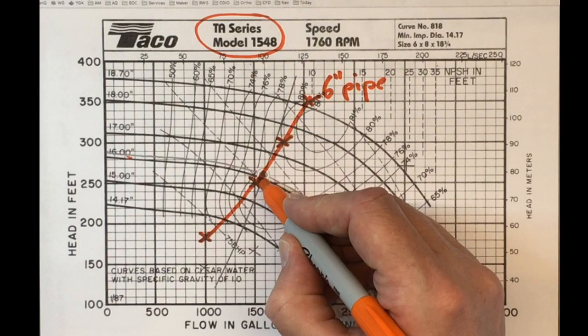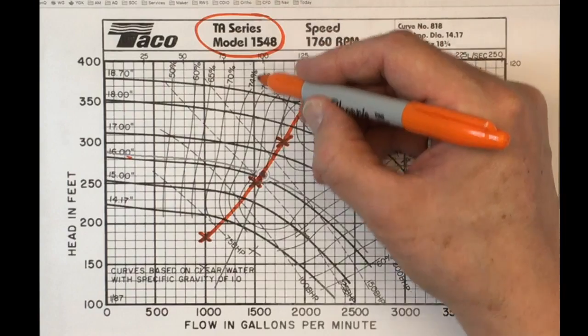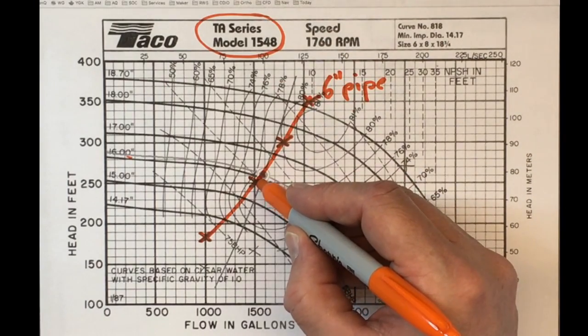We could maybe pick the 16-inch impeller, an off-the-shelf part. We'd get a little bit lower than our design flow rate, but that might work out okay.